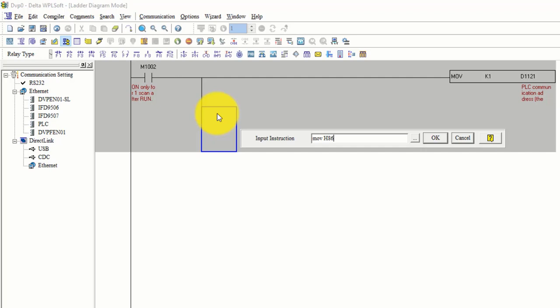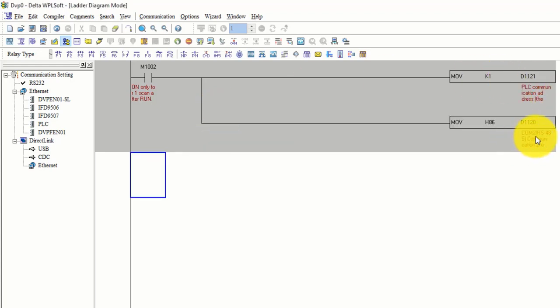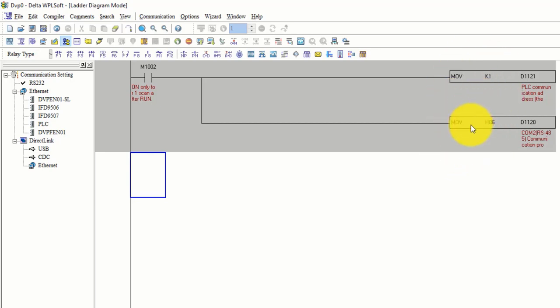After that you have to open COM2 for RS485, so you have to move the value H86 into D1120. This sets RS485 communication at the PLC COM2 position. As I told you in my previous lecture, you have to select ASCII mode, RTU mode, 8-bit data - the same settings must also be done in your slave PLC.